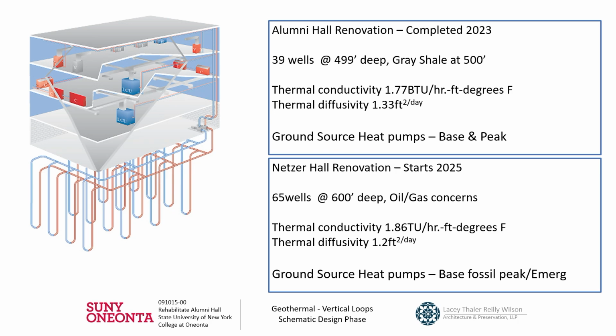Our Netzer Hall renovation is a larger project starting this fall. We're doing 65 wells at 600 feet deep. We did a test well last December, looking for 750 feet, but went down to about 660 before hitting refusal. There was some concern we might encounter oil or gas at that depth, but we didn't have real problems with the test well. The two buildings aren't too far apart and had similar conductivity and diffusivity figures.